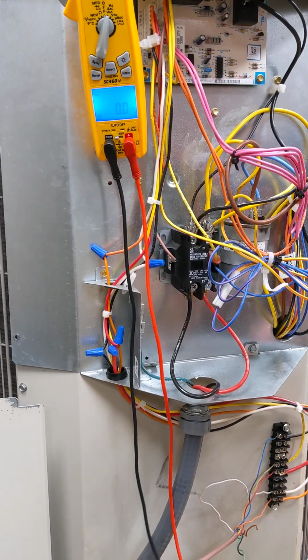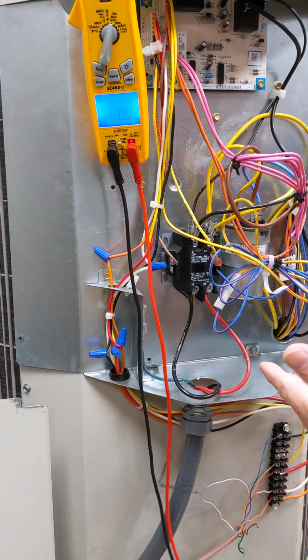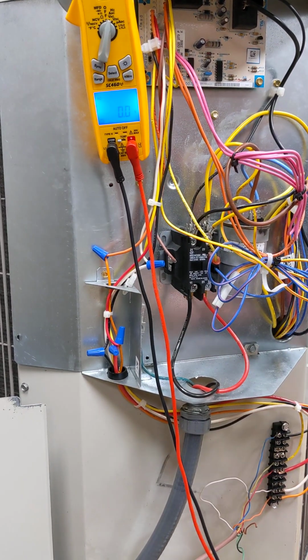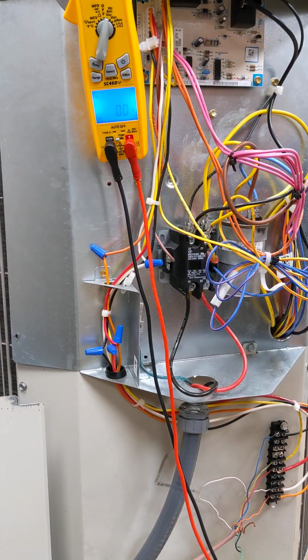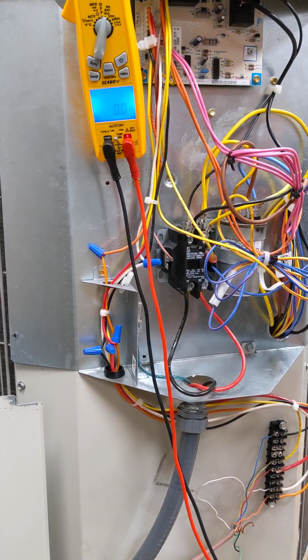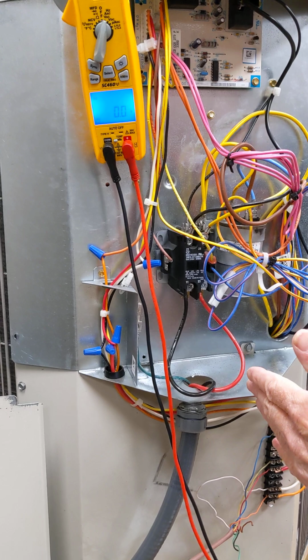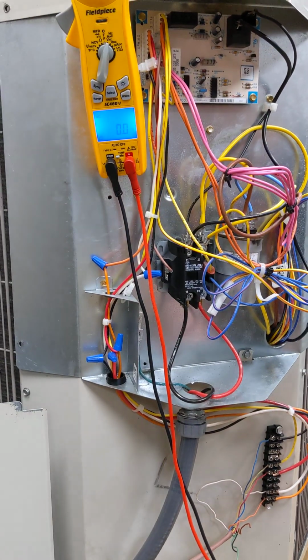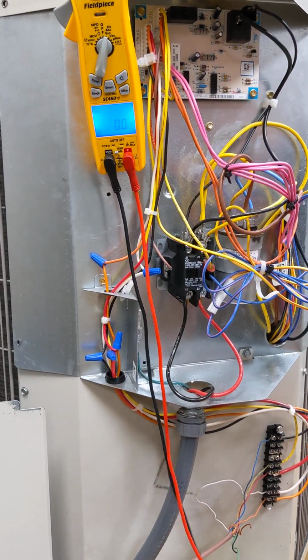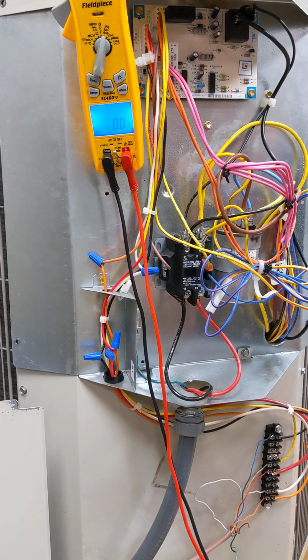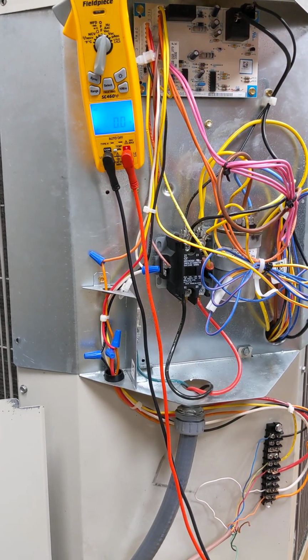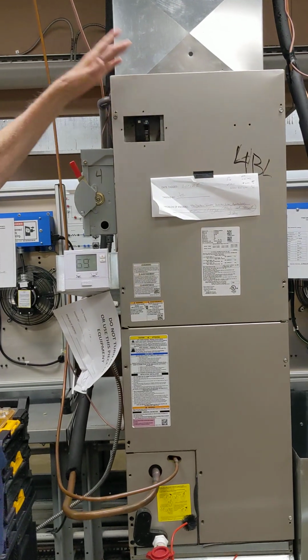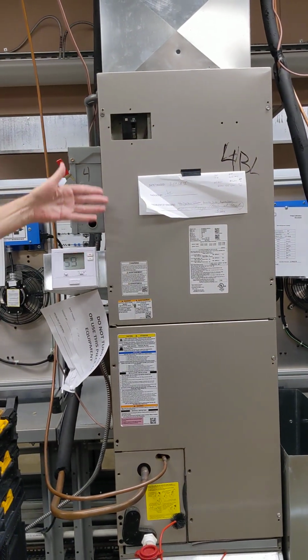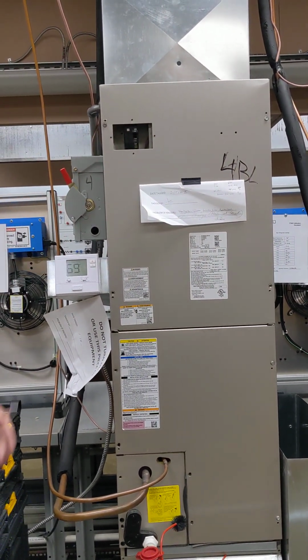I'm going to power up the unit. There are two different powers: the low voltage control power that comes from the indoor air handler unit, and the high voltage power to run the motors that comes from this disconnect. So I'm going to turn on the low voltage first. I should now have power going to the transformer that powers this.